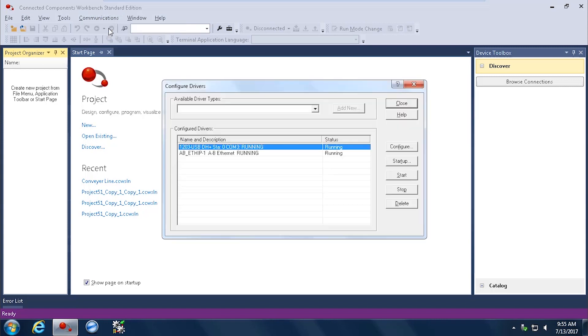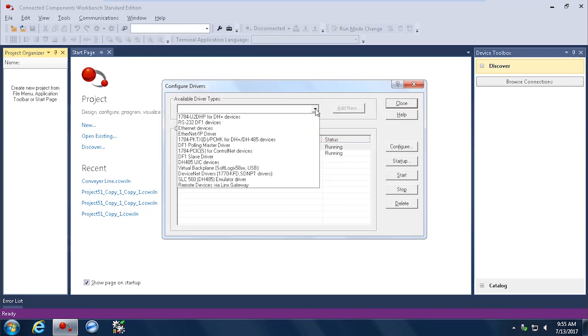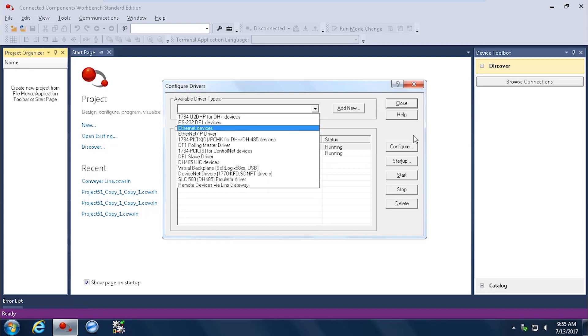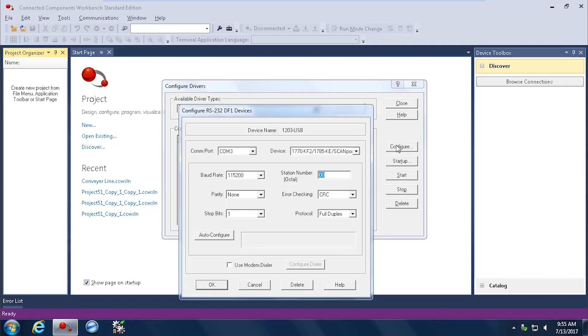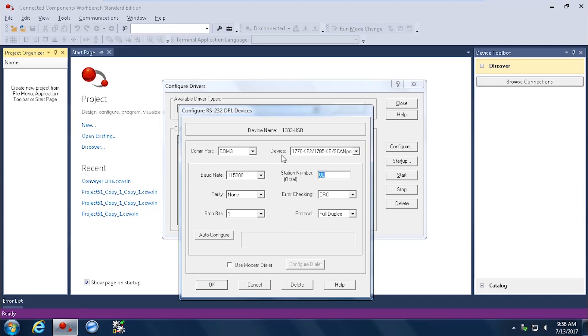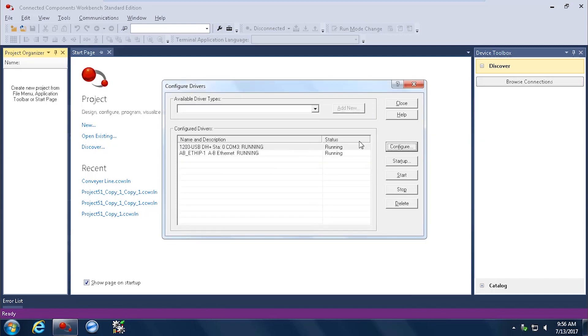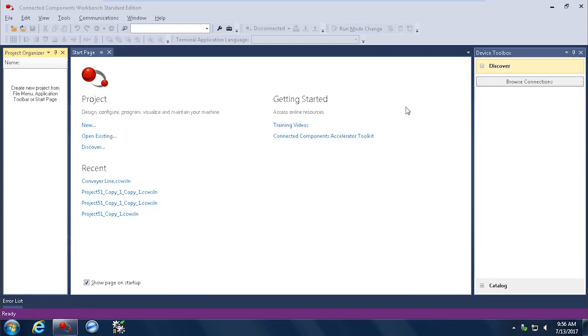In this case, you can select the available driver's screen, and you can see that there are multiples. And we're going to select the RS232 device driver, and we're going to call it 1203 USB. And this is how you configure it. You set up the COM port on your laptop. In this case, I'm using COM port 3. You set up the device for scan port 1770 KF2. The baud rate set up at 115200. And you can also do auto configure, but these are the common settings that are used for the RS232 1203 USB link. You can hit OK. And your driver's set up.